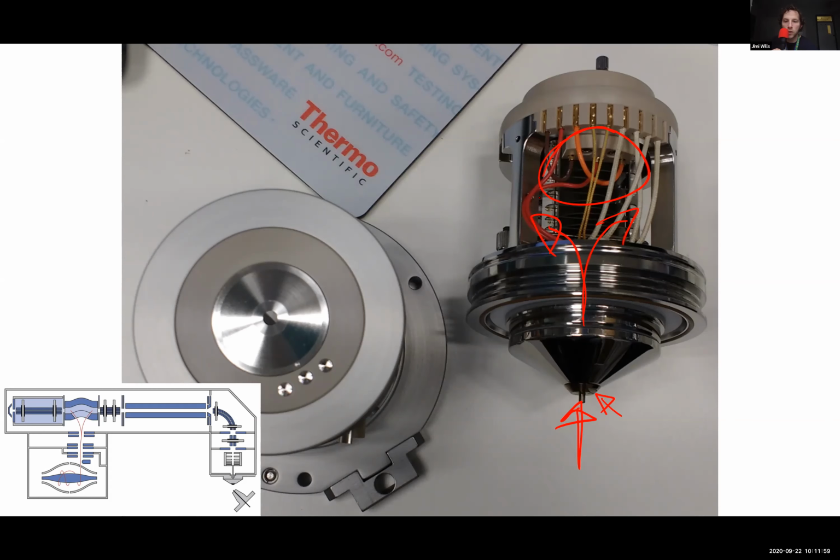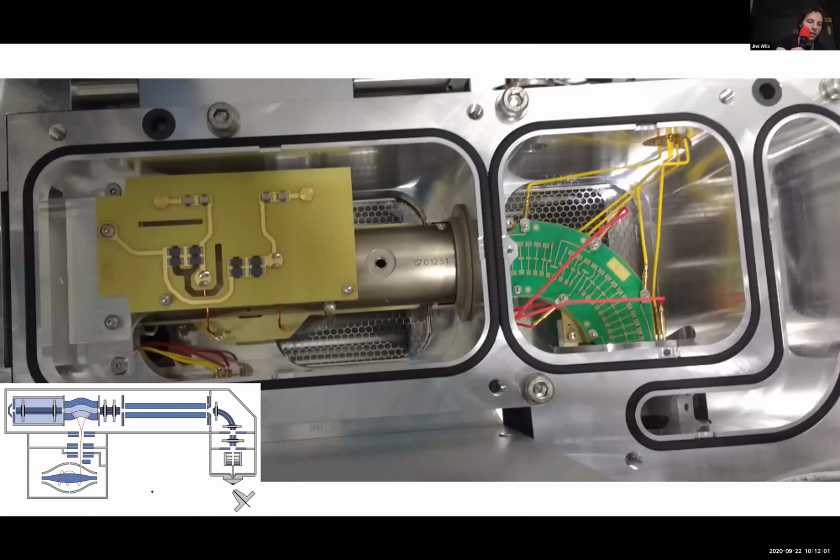This is now a view down the top of the mass spectrometer, and if you look at the schematic, this is the area we're talking about. Well, no, it's not actually, is it? This is the area we're talking about. So this little bit on the corner here is this bit here. And this is called a bent flatapole on this instrument. On the Fusion Lumos, it's called an active beam guide.